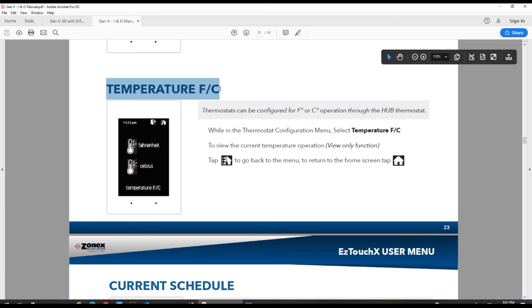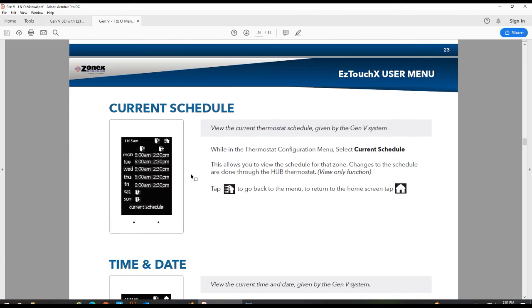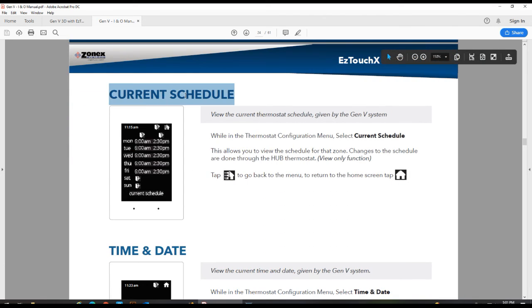Temperature format. This is a view-only option and allows you to see what the thermostat is set for. If you need to make any changes or something doesn't seem right, you can make those changes via the hub thermostat. From any thermostat, you can check the schedule that has been given to that zone thermostat via the hub. So go ahead and check it. If you see anything that looks wrong or needs to be adjusted, make those adjustments at the hub thermostat.